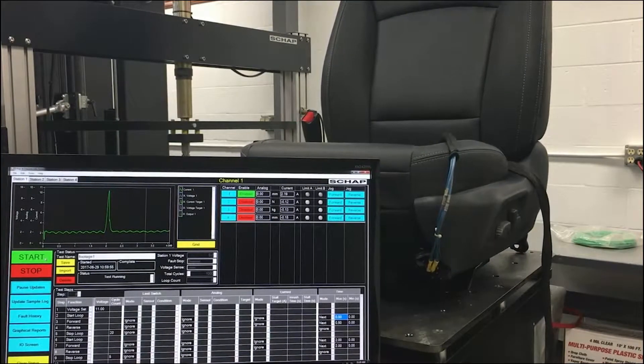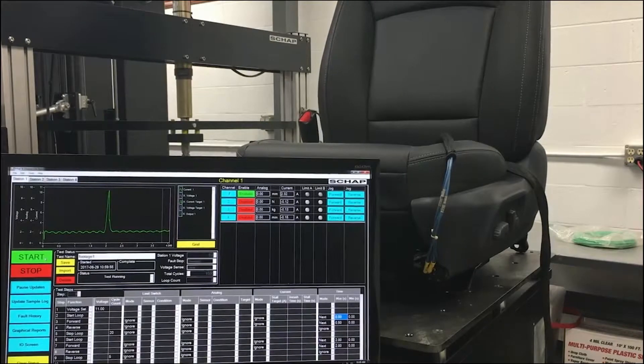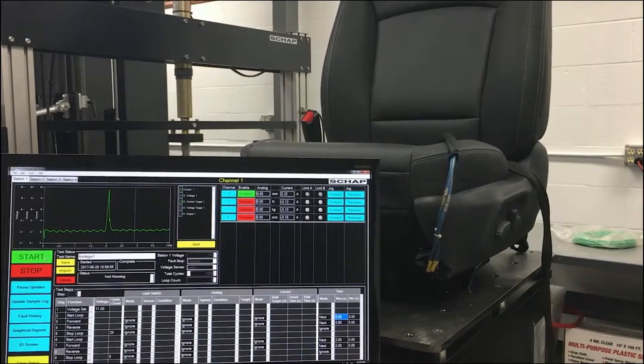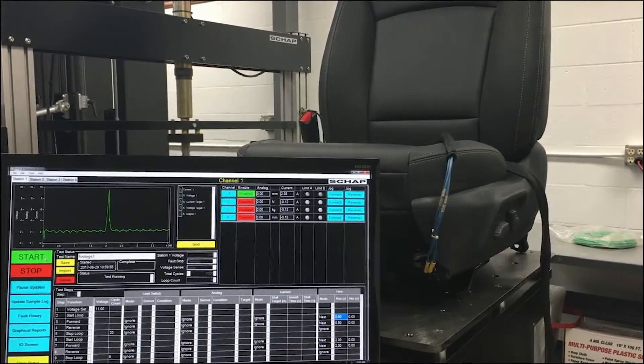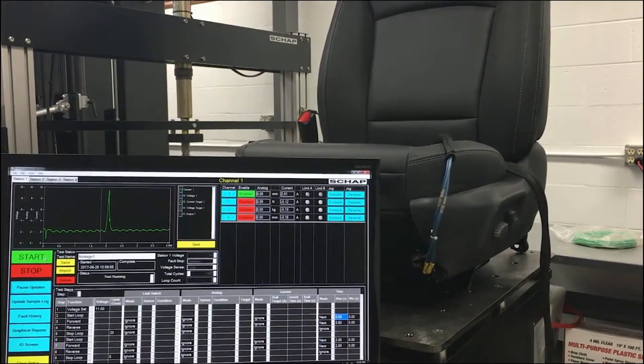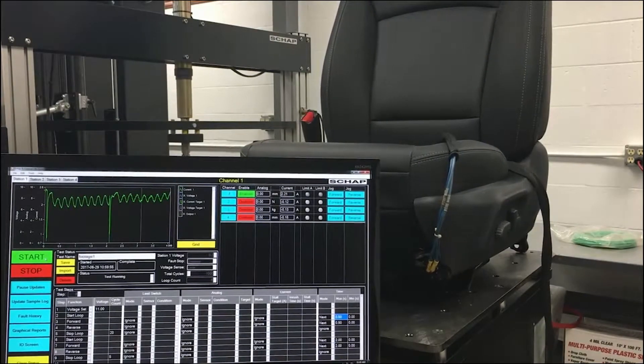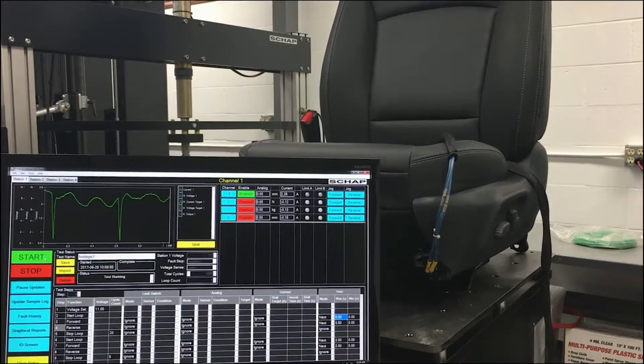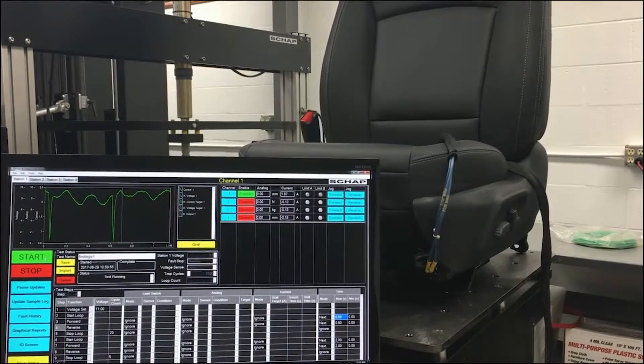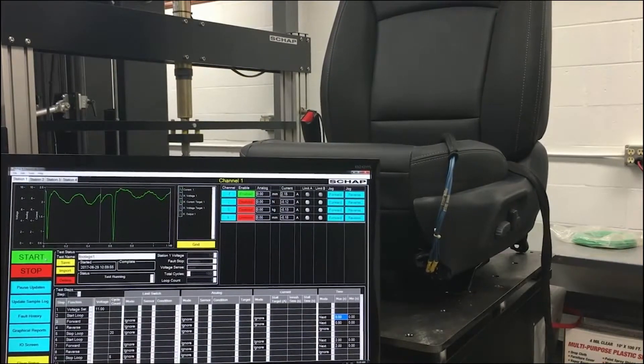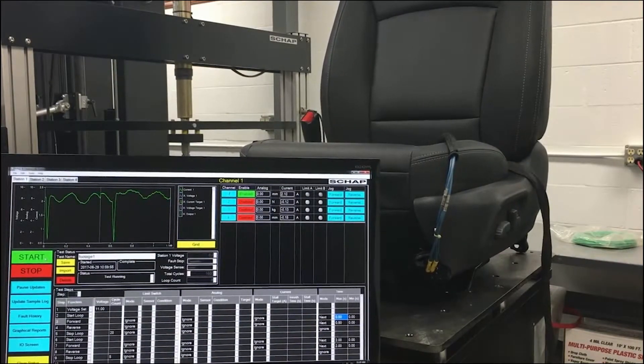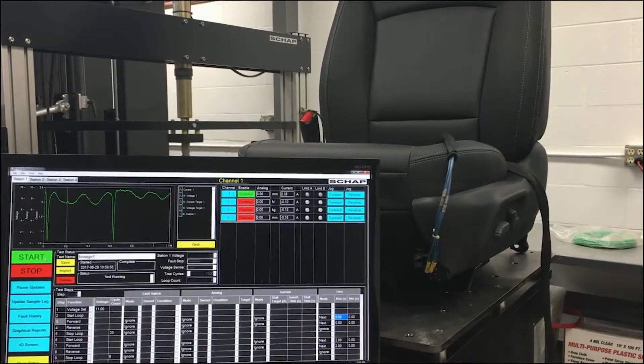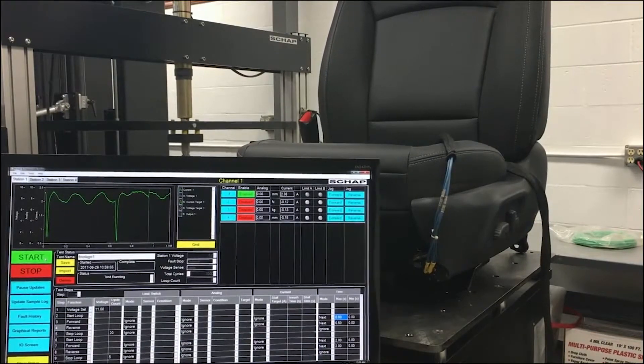Stall time: when the motor stalls, many test specifications require it to be held in the stall condition for some period of time. This parameter sets the delay in seconds after the stall target is sensed and the inrush time has elapsed, during which the tester should have kept the channel energized.